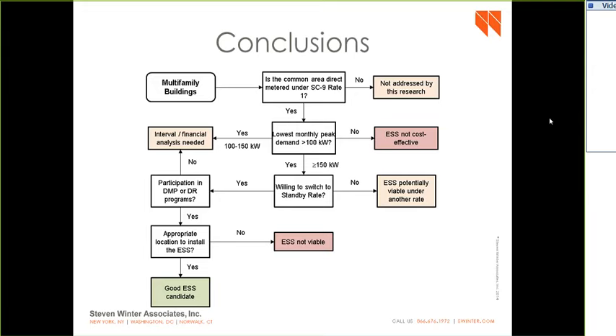And if it's outside, maybe zoning — is it within the zoning requirements? Occasionally we'll run into something goofy, like we did out in Marcus Garvey, where the obvious place the fire department wanted to put it was a really good spot, but it violated the zoning rule that you couldn't have equipment within a 30-foot offset of the back lot line. That was kind of dumb, because if it was a piece of air conditioning equipment, the zoning exceptions would allow for that. The guy in the zoning department told me the only problem was that the list didn't say battery storage — if it said battery storage, we could put it there.